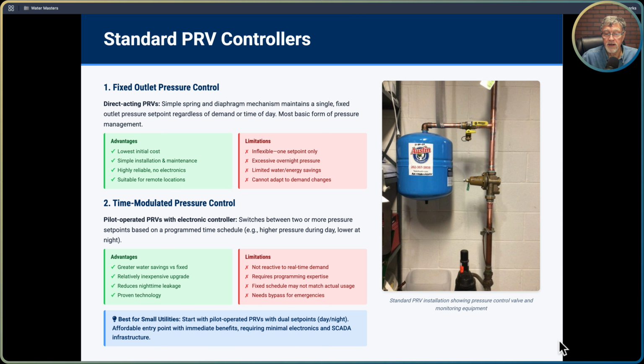It requires programming expertise, although not a lot. Fixed schedule may not match actual usage, so you're going to have to kind of pay attention, especially to seasonal fluctuations in demand, and it needs a bypass for emergencies. So best for small utilities start with pilot operated PRVs with dual set points, night and day, and then affordable entry points with immediate benefits require minimal electronics and SCADA infrastructure.